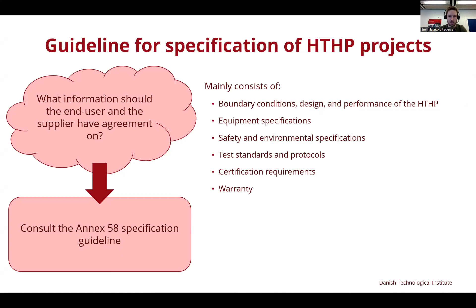It also lists a number of things to agree on regarding equipment: do you have material requirements, does it need to be stainless for example, do you need an intermediate loop on your heat exchanger because you're worried about leaks of refrigerant or oil? Also safety and environmental requirements, and testing standards that you as an end user feel must be performed so that you know the heat pump lives up to whatever standard you require, etc.